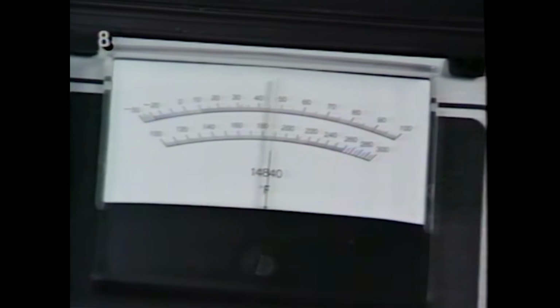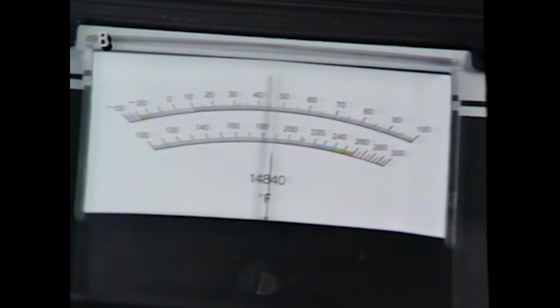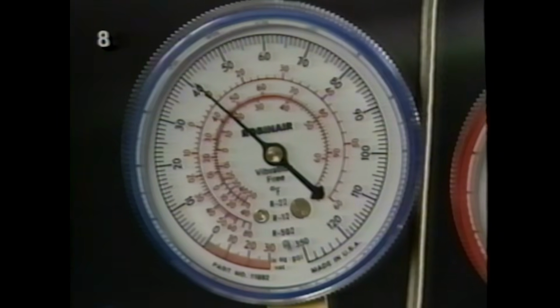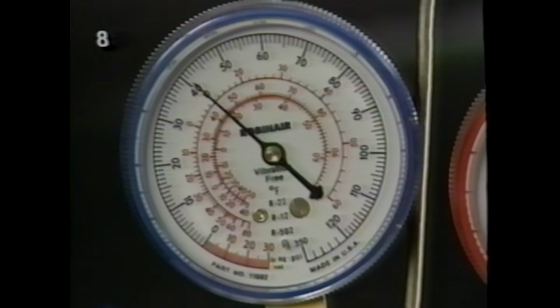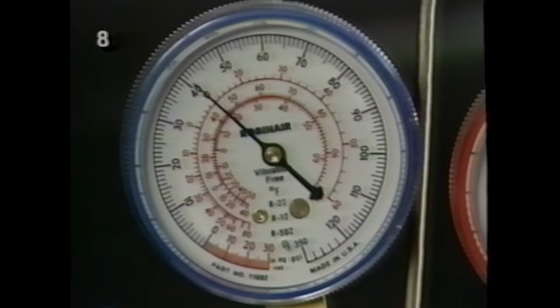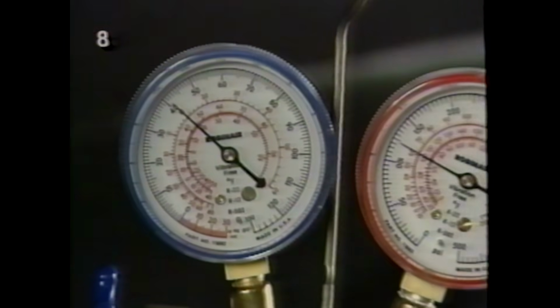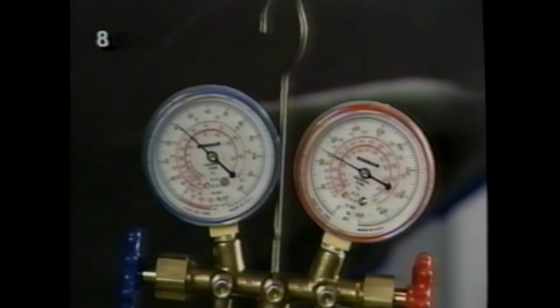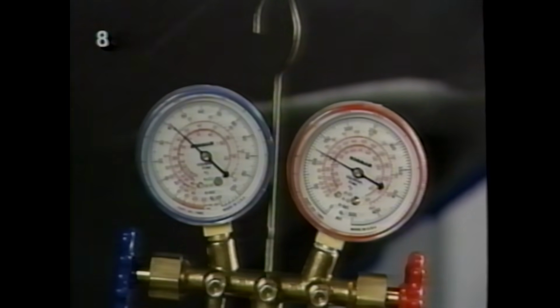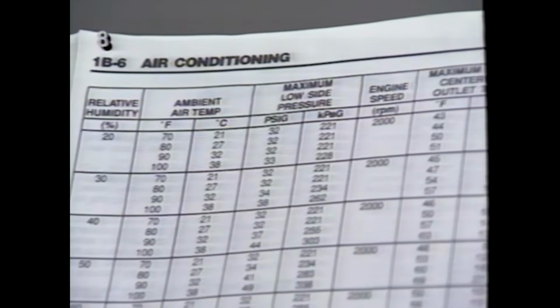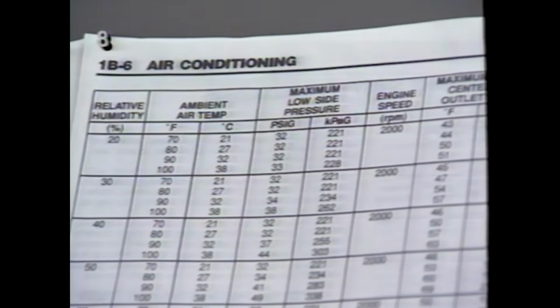It should be in the 40 degree to 50 degree Fahrenheit range if the system is performing okay. The accumulator low pressure gauge will be in the 23 to 49 psi range. If it goes below 20 psi or over 51 psi, the cycling pressure switch isn't working properly. And the high pressure gauge will read in the 150 to 250 psi range, depending on outside air temperature conditions. Remember to check the service manual performance data for exact specifications. And in hot weather, measure the air temperature in front of the condenser to select the right data.